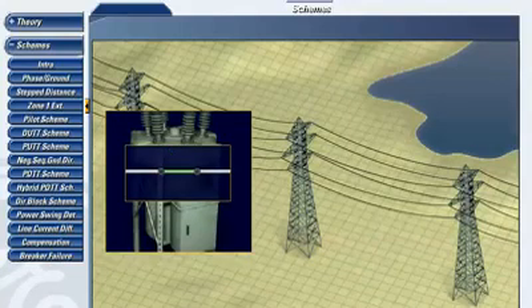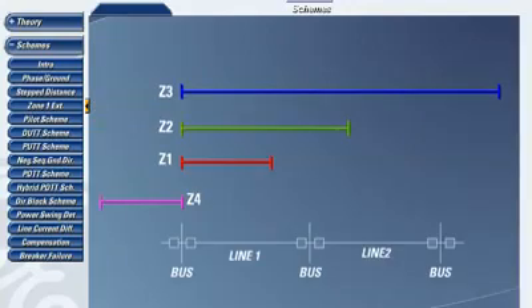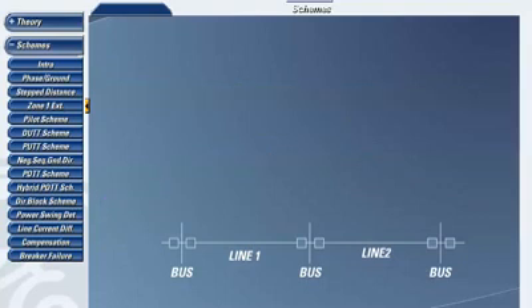As mentioned before, the Zone 1 extension scheme is like the stepped distance scheme, where it has 4 zones of protection. The difference between the two schemes is that in the Zone 1 extension scheme, an additional Zone 1 impedance setting is set higher to overreach into the next adjacent transmission line. The impedance of this extended Zone 1, which is labeled Z1X, is usually set to the same impedance as the Zone 2 setting of 120% of the impedance of the entire transmission line.